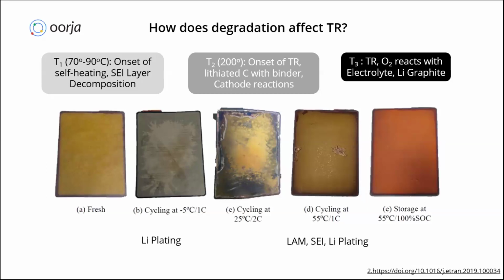At T1, certain reactions start. At T2, both electrodes get exposed and cathode reactions start. Then at T3, oxygen reacts with the electrolyte and the cell reaches Tmax. T1 and T2 are the critical temperatures, one below 100 degrees and the other around 140 to 200 degrees Celsius.